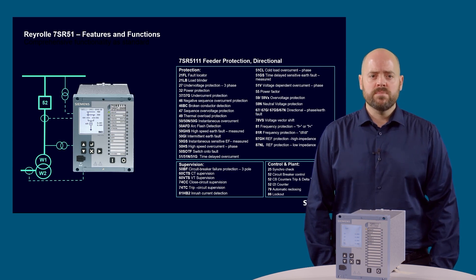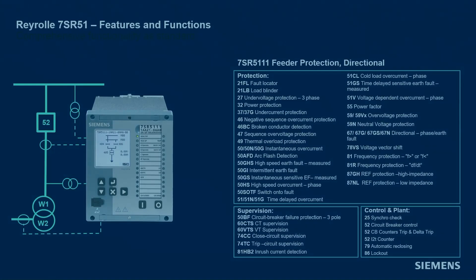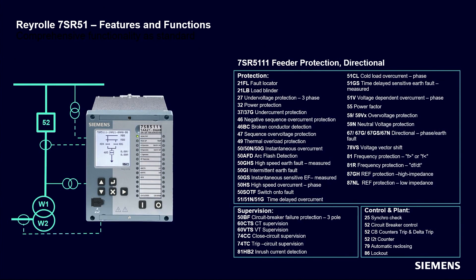With the addition of voltage inputs the device has all associated protection functions, including directional overcurrent protection function 67 — allowing each element to be set to forward, reverse or non-directional operation — under and over voltage, vector shift, power and frequency. Load blinders function 21 are used in conjunction with overcurrent protection in distributed generation systems, and directional control of measured and calculated earth fault elements provides comprehensive network protection. The 7SR5121 will detect earth faults in all networks including isolated and compensated networks.